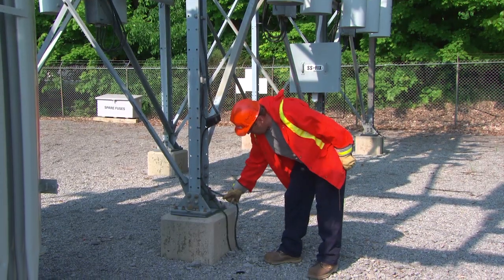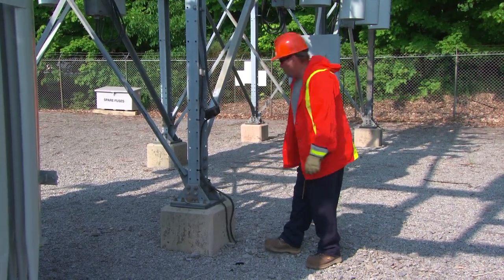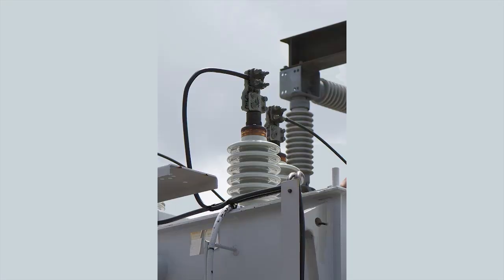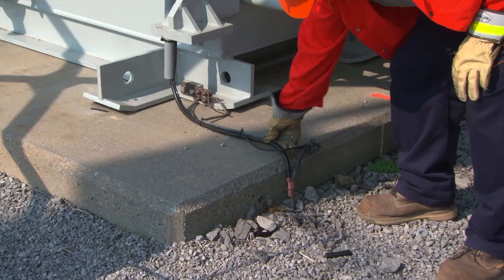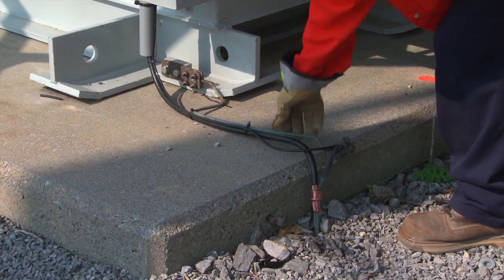Ensure there are no missing or broken grounds or neutrals. Pay particular attention to the neutral connection between the transformer bushing and system neutral, as this can sometimes be compromised due to copper theft. Also, check the location of the ground connection.